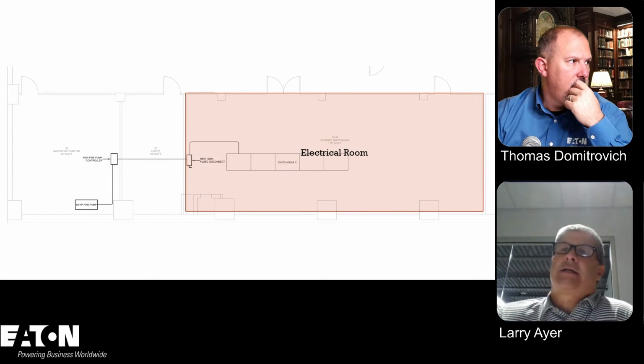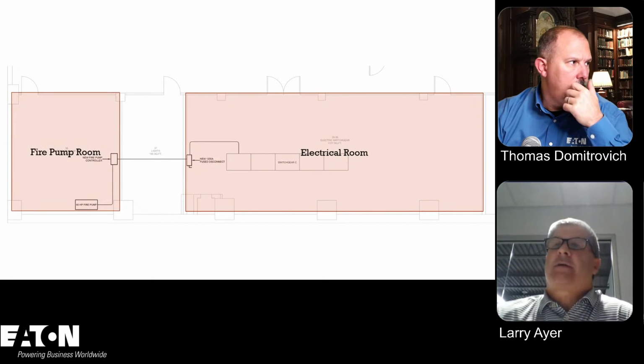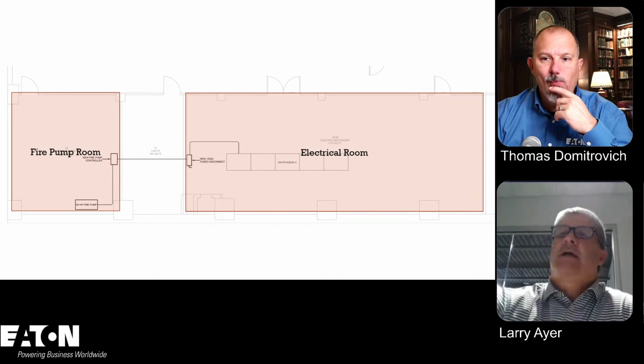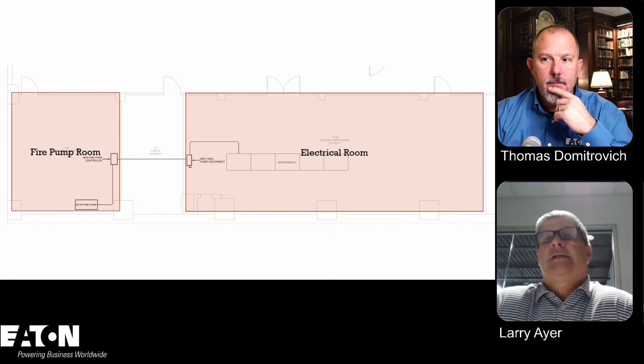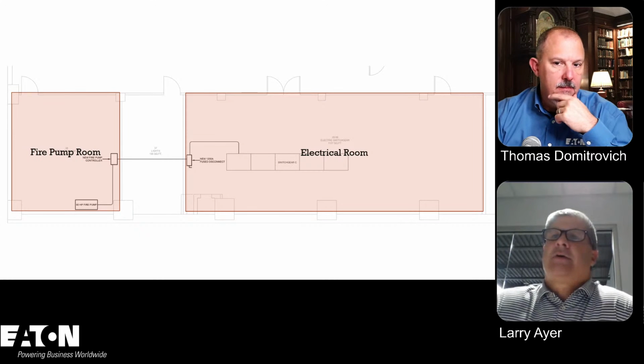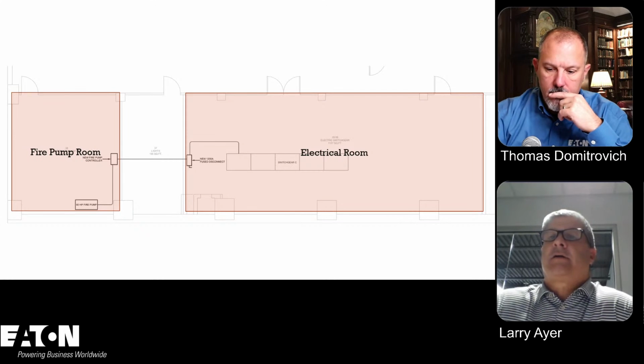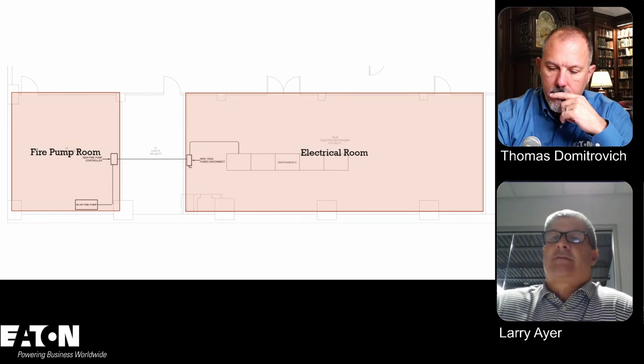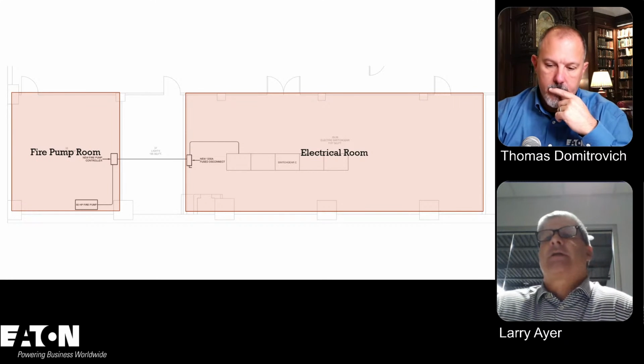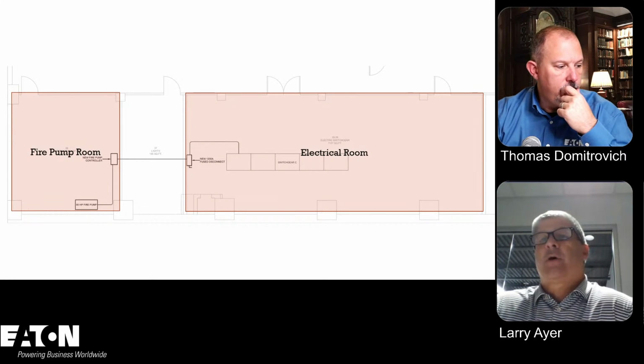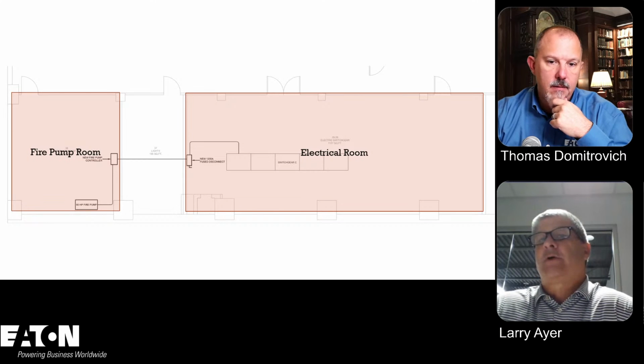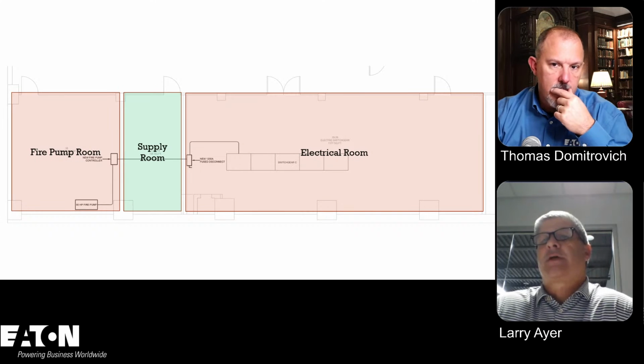I hope everybody can see it. This is a job we're doing here, and it came up the other day, and I thought it'd be interesting to put this up there because it shows some of the challenges you have. For instance, you have an electric room on the right and the fire pump room on the left, and then there's a small room in between. You do not have to protect for a 2-hour rating if you're in the electrical room or the fire pump room. But if you leave those rooms, you have to protect it for 2 hours. So you have to make a decision there.